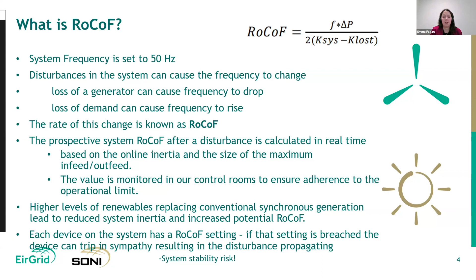Every device on the system has its own RoCoF setting, and if that setting is breached, that device might trip in sympathy, and therefore you'd actually propagate that disturbance. So this would lead to a system stability risk, which we don't want. So what did we do?